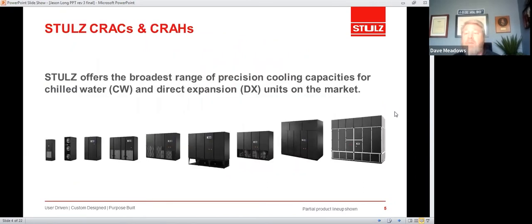With that out of the way, I didn't want to spend a lot of time today talking about traditional CRACs and CRAHs, but I thought this would be a good place to start. CRACs, also known as computer room air conditioners, are DX units designed for the white space or the data center. And CRAHs are computer room air handlers, which are chilled water units designed for that same space. We have a very diverse offering of products. If you take a look at the slide here, it pretty much covers the gamut from our smallest units that run around 2 tons per unit to our largest CRAH units, which currently are about 300 tons per unit of high sensible cooling.